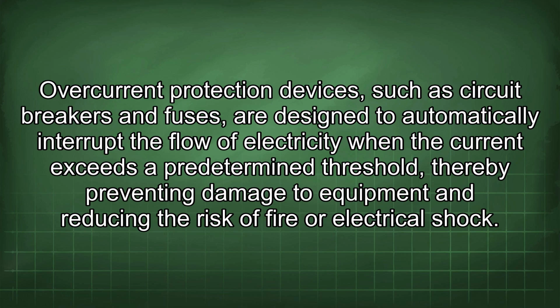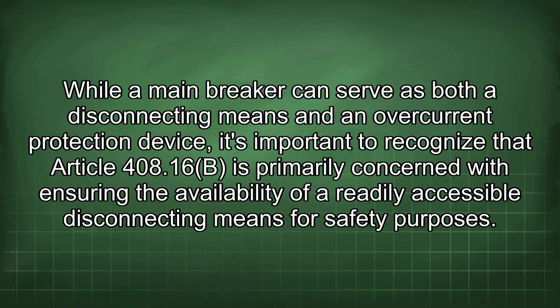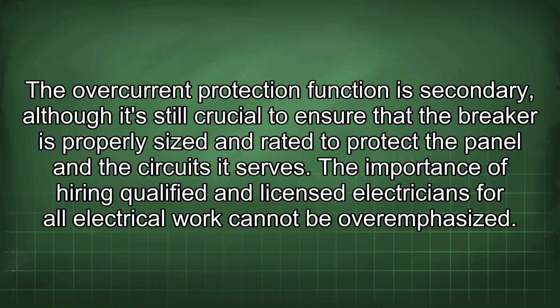electrical shock. While a main breaker can serve as both a disconnecting means and an overcurrent protection device, it's important to recognize that Article 408.16(B) is primarily concerned with ensuring the availability of a readily accessible disconnecting means for safety purposes. The overcurrent protection function is secondary, although it's still crucial to ensure that the breaker is properly sized and rated to protect the panel and the circuits it serves.